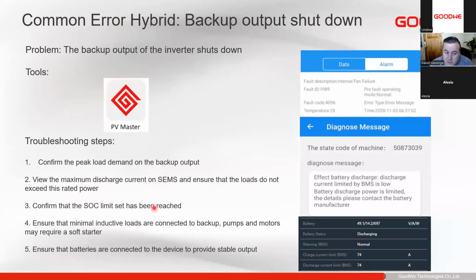Also, next we can confirm the SOC limits. Sometimes the SOC limit on the on-grid and off-grid are set incorrectly, and then the device has reached its set point and it switches off. If that happens, you'll have no error codes, no warnings, nothing of those sort, because the logic says I'm going to switch off now, so it switches off. It's not a fault, it's a setting. So just double check that these settings are correct. From the install account, you can also view that remotely.